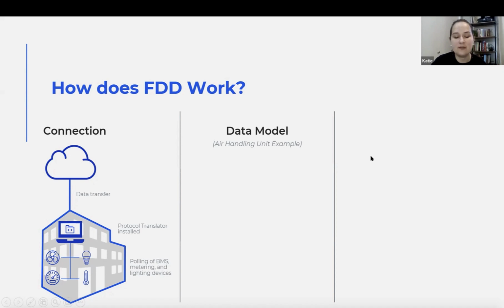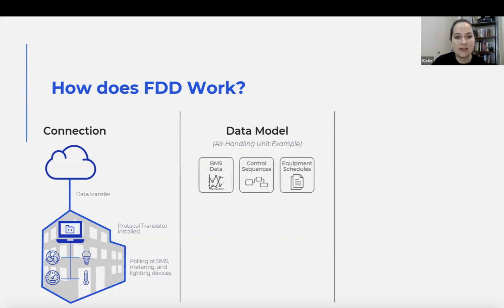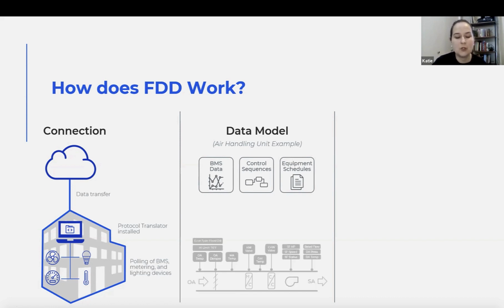So the next phase is the data model. We're going to use an air handler as an example. You're going to take your BMS data, your control sequences, and your equipment schedules, and I'll give you an example with an air handler of how that works. Right here below, you have a typical AHU. It's 100% outside air. It's got some dampers, some coils, some fans, some temperatures. So your FDD system will take that BMS data. It'll pull in your outdoor air temperatures, and any of the data that it needs to make those conclusions.